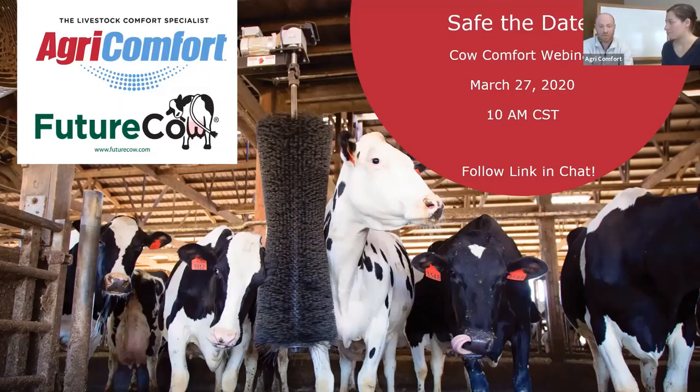And you get those cold days in the fall and the spring where it's right around freezing or a little below freezing and it's damp and humid. Those days are colder to me than the -10 or -15 Celsius days where it's dry. And so really the only way that you're going to be able to deal with that moisture, if it's not drafty, is to increase your ventilation rates. It's not going to reduce the humidity in the barn, because we're ventilating with high humidity outside air. But if you increase your ventilation rates in a manner that's not drafty, we still get more fresh air. I mean, it's not the most satisfying answer, but that's one option.